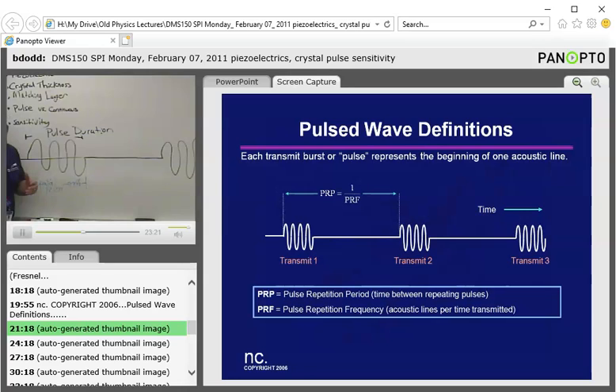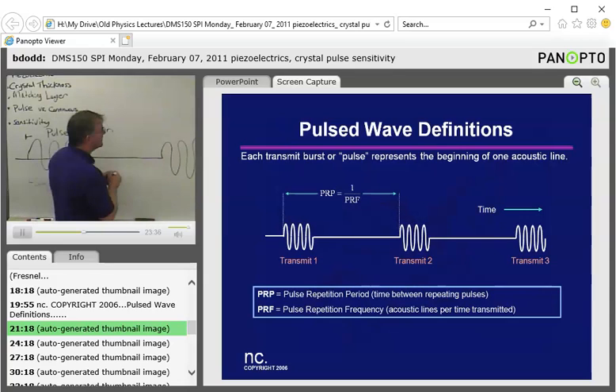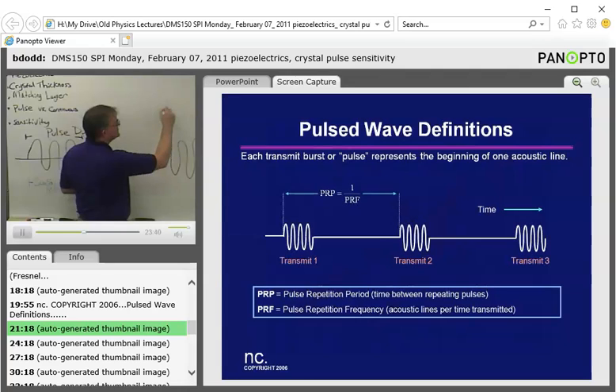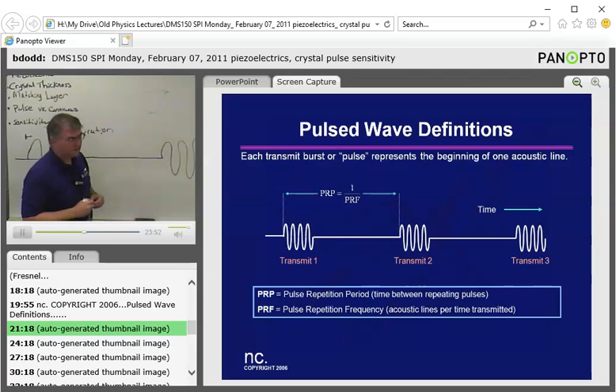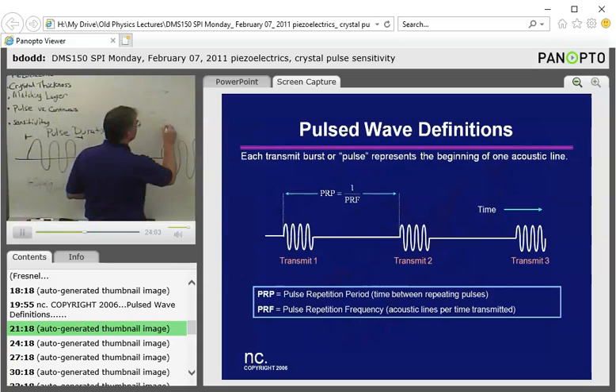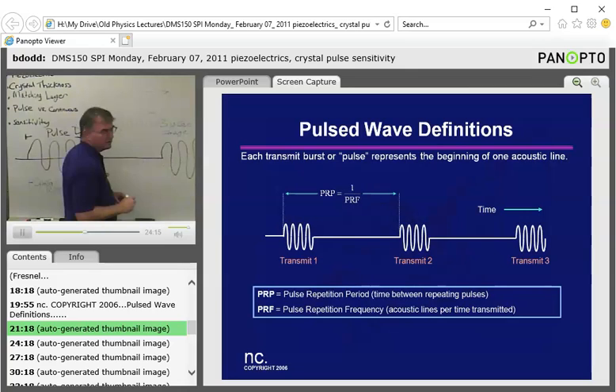Now when we send out a pulse, if I want to image 1 centimeter deep, how long do I have to wait before I send out another pulse? How long does it take for my sound wave to go from the surface of the skin 1 centimeter deep and then come back so I can hear all the echoes that will come back from that? 6.5 microseconds to go 1 centimeter deep. Another 6.5 microseconds for the echoes to come back. So that's a total of 13 microseconds to image a depth of 1 centimeter.